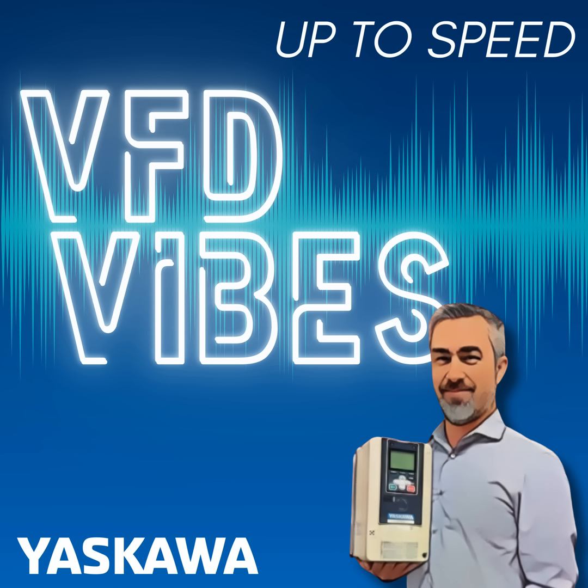There are a number of revisions of IEEE 519 from 1992, 2014, and then the most recent revision, 2022, that outlines parameters for your electrical system in terms of how much THDI, that is total harmonic distorted current, and THDV, that's total harmonic distorted voltage, is considered acceptable.